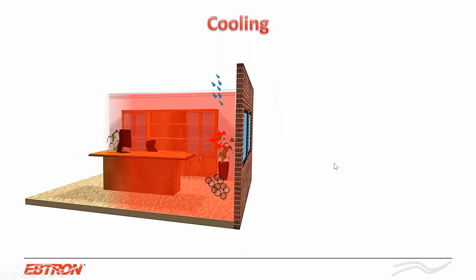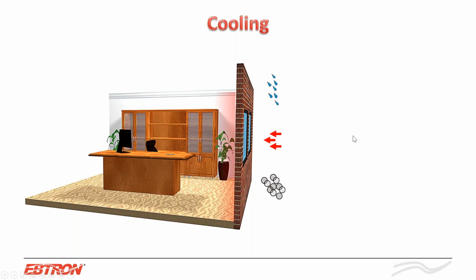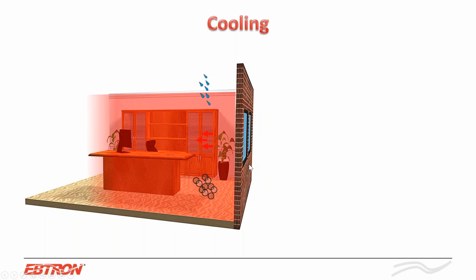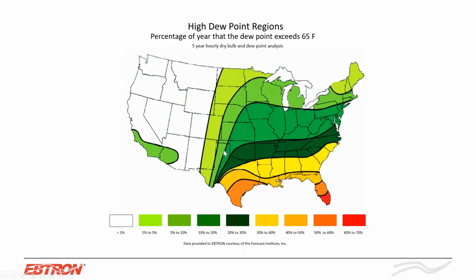And this is just showing an example, like in the summer when you're doing cooling and you have a negative space, you're bringing in this moisture to the space. And normally for mold and fungal growth, favorable conditions are above 65 degrees Fahrenheit for your dew point temperature. And as you'll see, even in the Massachusetts area, that's almost 10 to 20% of the year where you have these conditions favorable for mold and fungal growth. And what does that mean? That means almost 2 months out of the year, if you're not maintaining proper building pressurization, that could lead to potential mold or fungal growth in your space. And what does ASHRAE say about this?